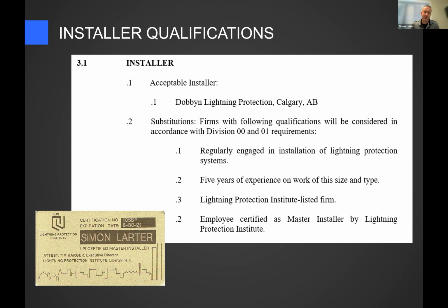City of Edmonton says do a risk analysis. If the risk analysis shows you're supposed to have it, you're supposed to have it. Other than that, there is no hard requirement for a private citizen, a private company, or anybody building anything, other than a nuclear facility or a nuclear material storage or generation facility. Those are the only times the hard requirement for lightning protection kicks in. Otherwise, you're not required to.